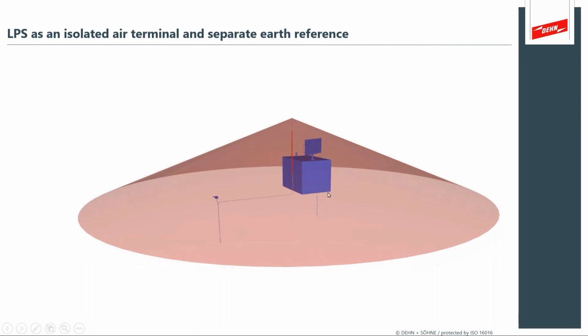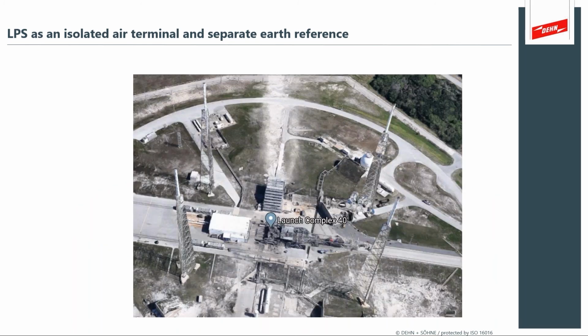Unbonded metal would produce arc and spark, and it would produce things like incendive sources and noise into the electrical system. So unbonded metal is really a big problem on sites. We also talked a little bit before about isolated air terminal systems for very expensive assets like a rocket filled with rocket fuel and hydrogen and oxygen, where the introduction of lightning side flash would essentially destroy the asset. And so we see isolated air terminal systems that effectively provide lightning protection with separation from the victim. So you're either separating from it or you're bonding to it.